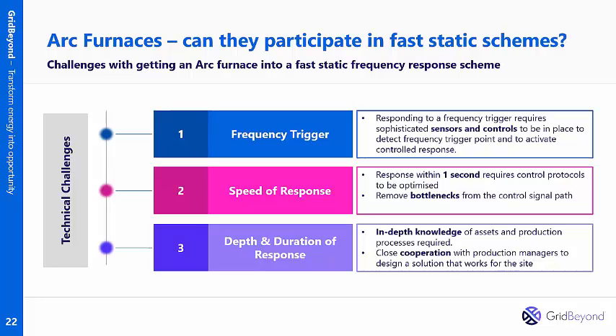The things that are important to us and to the grid are the frequency trigger. What the grid requires is for you to shed your load within 1 second when the frequency dips to a certain trigger. We then require high-speed monitoring and high-speed control, first to capture the load shedding, then to shed the load within 1 second. Our platform has this high-speed monitoring, and it's able to send these signals in milliseconds to deliver this in time.